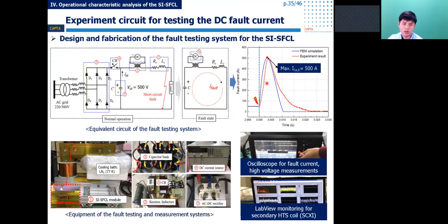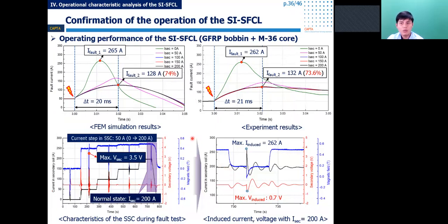And here is the fault current result in the experiment compared with the FEM simulation. This is the equipment of the fault testing system and measurement system. In the fault testing, the fault limiting characteristics of the SI-SFCL were confirmed with different secondary operating currents and then compared with the FEM simulation result. As you see, the experiment result was similar to the FEM simulation result. With the secondary current of 200 ampere, the fault current was limited up to 73.6%. During the fault test, the induced current and voltage in the secondary coil were quite low, which didn't affect the DC bias current source and secondary coil operation.